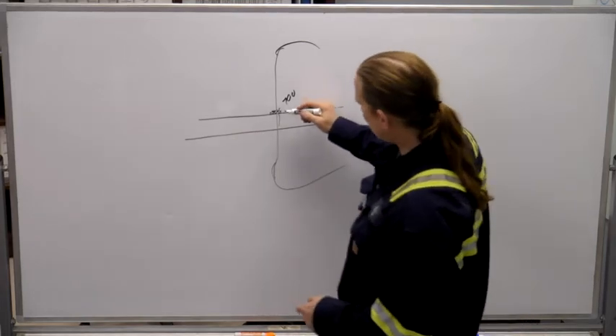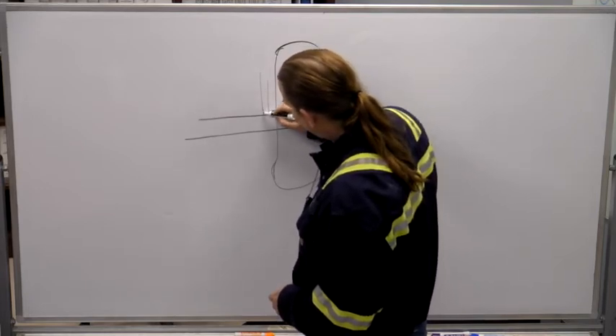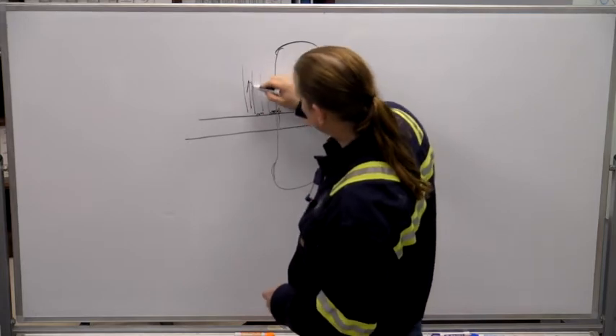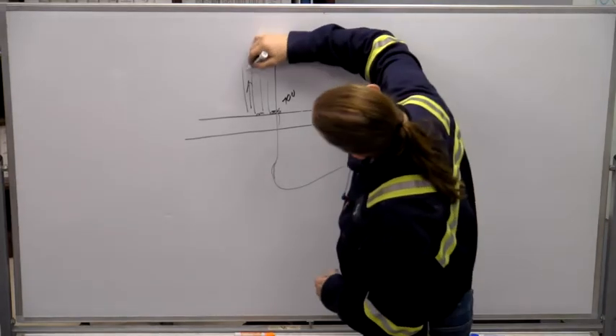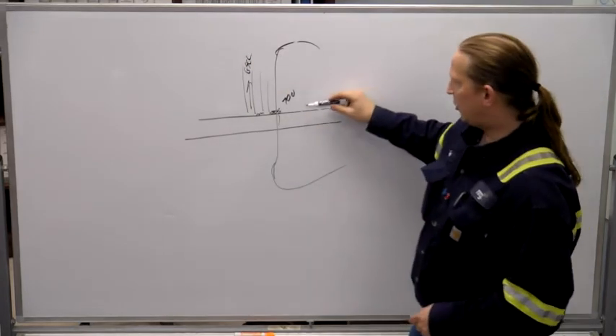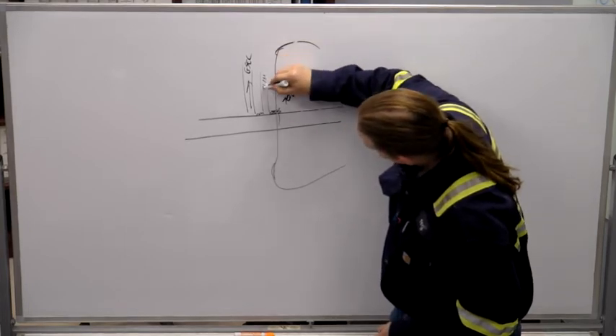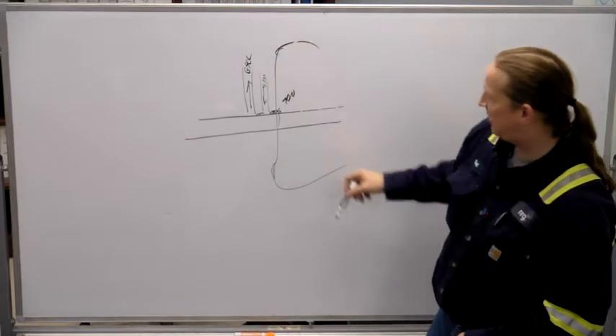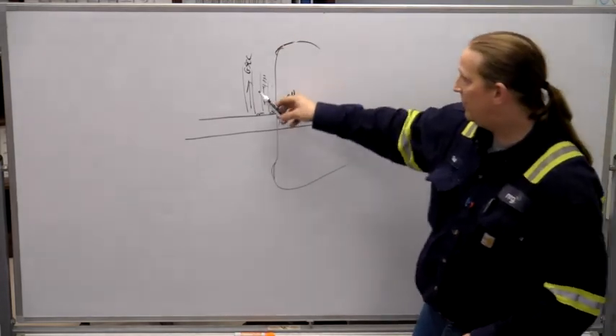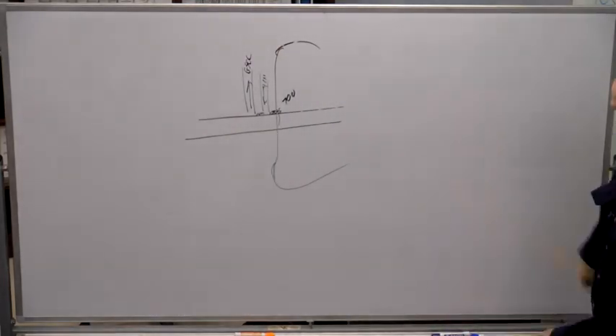So we said we had 700 pounds of steam trying to get out. So then we've got a steam header, and then we've got more labyrinth seals. So the steam that leaks out, you've got four pounds of steam that is being pushed in, and you've got whatever steam is leaking out. And then you've got the gland steam exhaust condenser that is catching all the rest of the stuff and sucking it off and turning it to water. And then it goes back to the condenser through the miscellaneous drain.